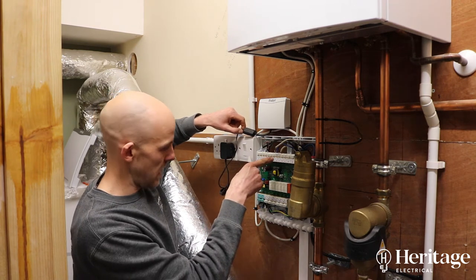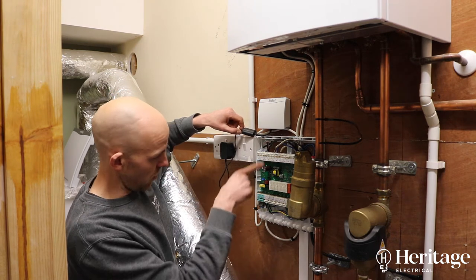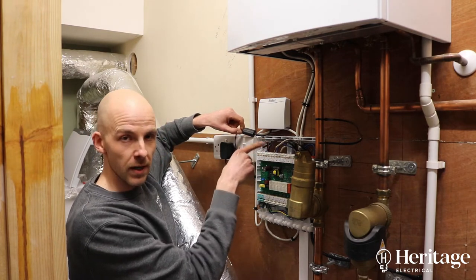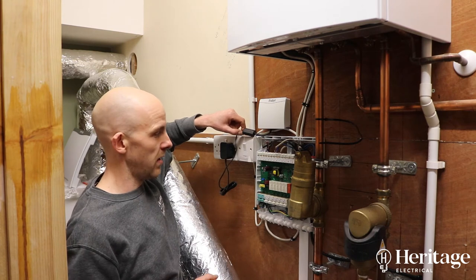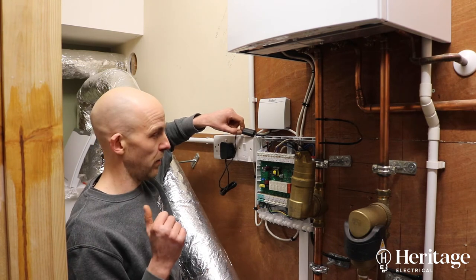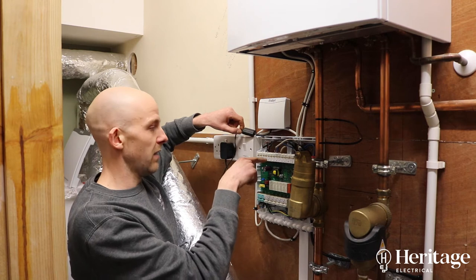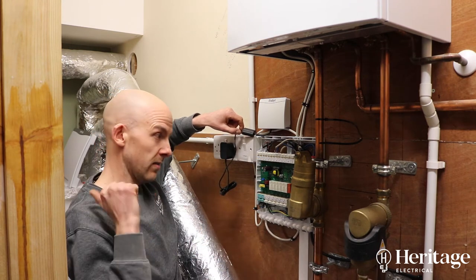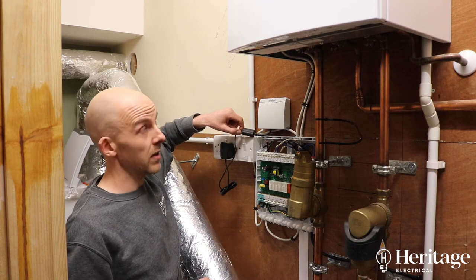You can see S7 here which relates to R2. This is the switch coming from our third-party Heatmiser system for the underfloor heating, so that is giving us a switch here to fire the boiler and send heat over to the extension.